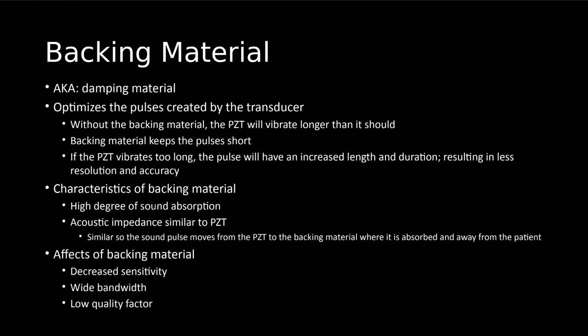Next, we have our backing material. So this is kind of a bizarre concept. If you're a little confused by what the backing material does, that's okay. The textbook also makes it a little bit more confusing. So don't think about the backing material too much. What we're basically doing with this is we are reducing the free vibration of the sound wave. So we have this sound wave that's produced in our transducer, and it wants to go off and sing and do its own thing. We're basically saying, no, you can't sing that loud, or you can't sing that song. So we're giving it limitations to what it wants to naturally do.